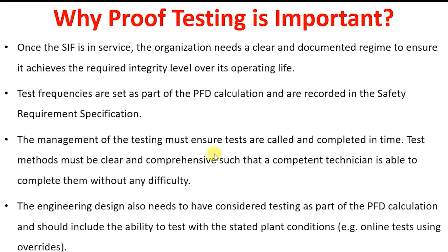The management of the testing must ensure tests are called and completed in time. Test methods must be clear and comprehensive such that a competent technician is able to complete them without any delay. Engineering design also needs to have considered testing as part of the PFD calculations and should include the ability to test within the stated plant conditions. Online tests using overrides, in case of any online test performed using an override, also need to be captured.